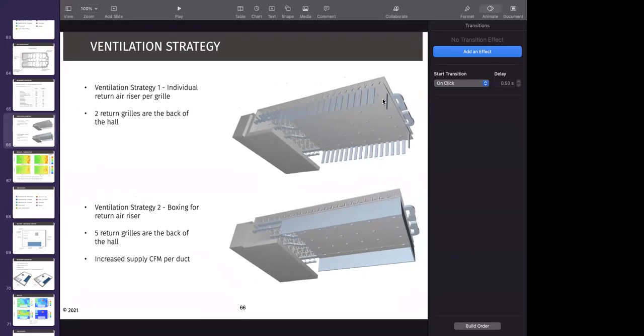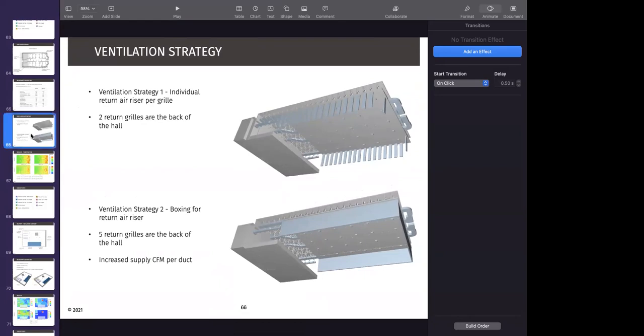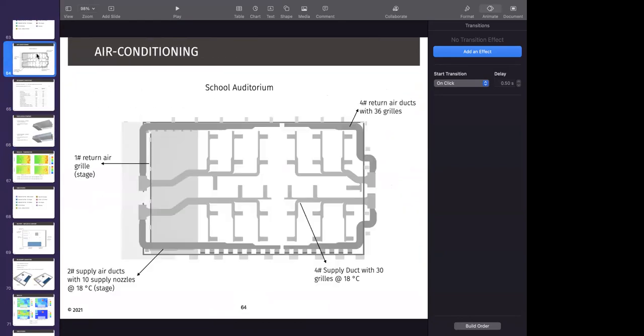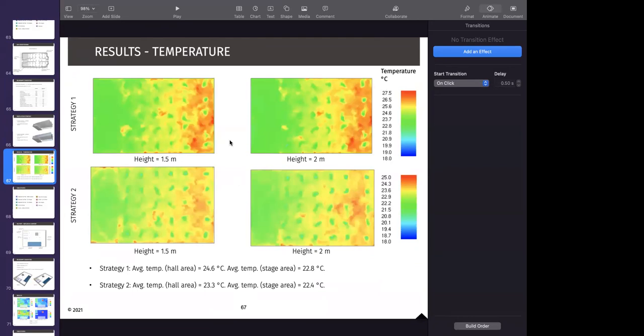And the CFM from the grills, these are the supply grills on the false ceiling, the CFM through that was increased to get a bit more cooler air coming down. If you see, the supply temperature is at 18, but by the time it reaches the bottom of the hall, it comes to around 20 degrees. So giving that higher CFM just makes it a tiny bit cooler, and having the number of return risers increased at the back, there is more extraction of heat at the back, which reduces the heat accumulation.